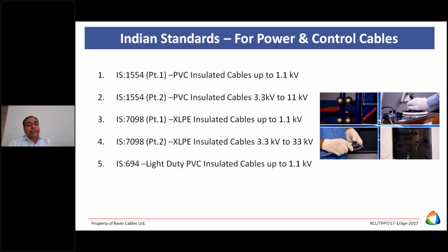where people are using XLP insulation, because XLP insulation has a breakdown voltage of 40 kV per mm. However, in case of PVC, breakdown voltage is around 20 kV per mm. So breakdown resistance capability is much higher in XLP. So normally today we are using XLP insulation for fixed installation. Suppose it is a flexible installation, then EPR rubber is used up to 33 kV. And nowadays new technologies are available where polypropylene compounds are used for 220 kV cables. As per the customer requirement, site requirement and system requirement, voltage ratings are defined and cables are designed accordingly.